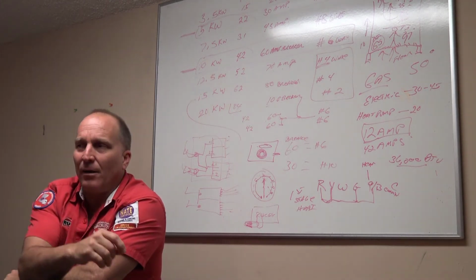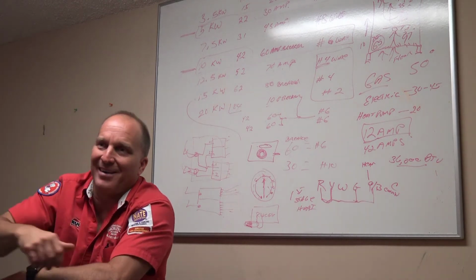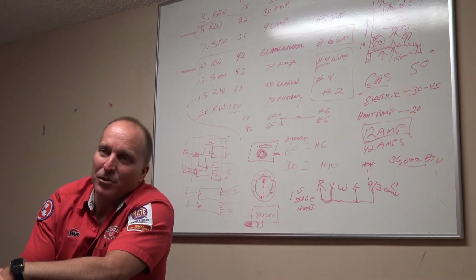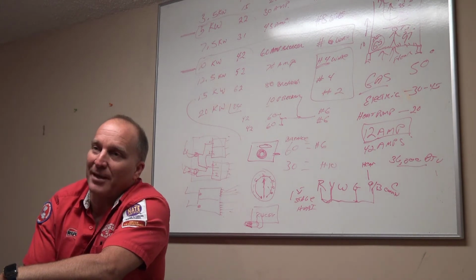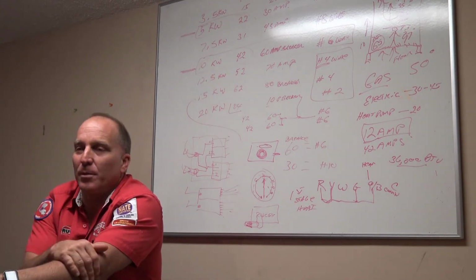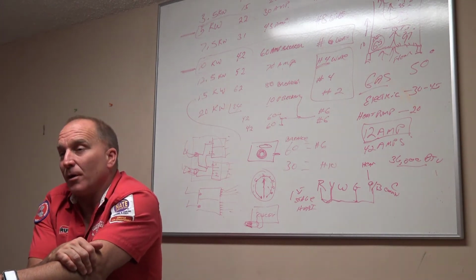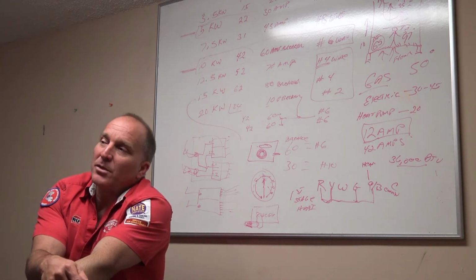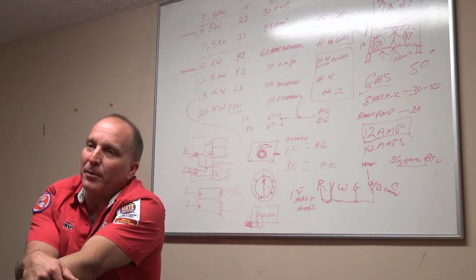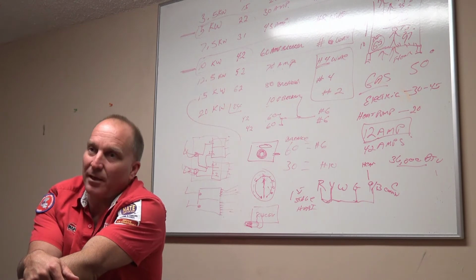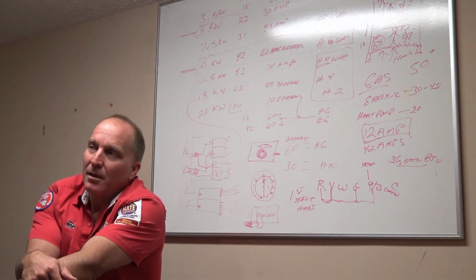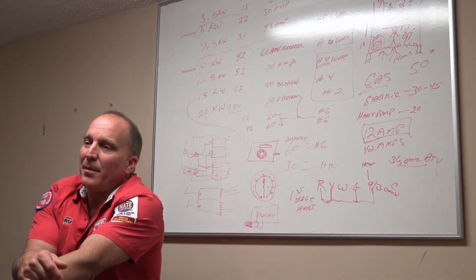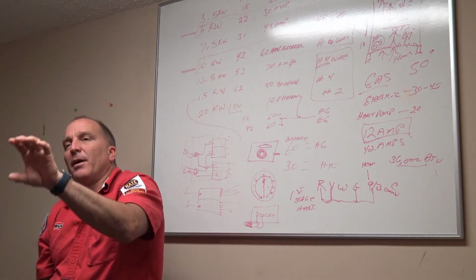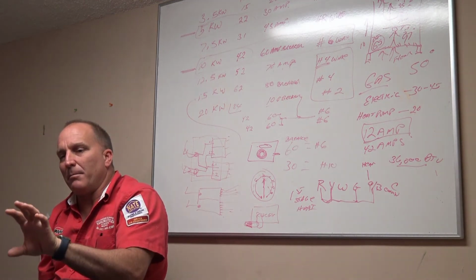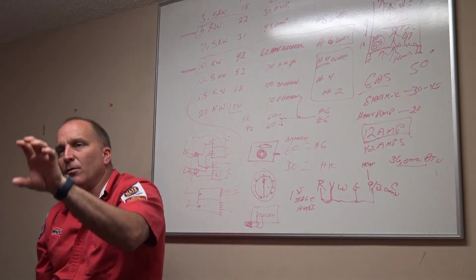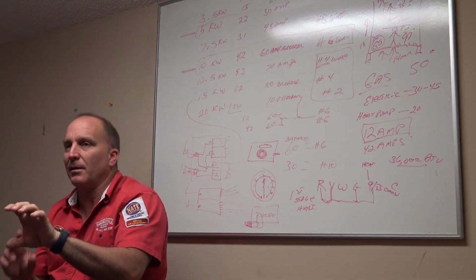Can you sand it down? No, it's got 240 volts to it. You can't do that either. But you know what you can do? See if there's another open space and move the breaker to it. Another thing you can do: what draws the most amperage in that house? Probably that electric heating element. So I may take two or three breakers above or below it and move them up or down to take another space.